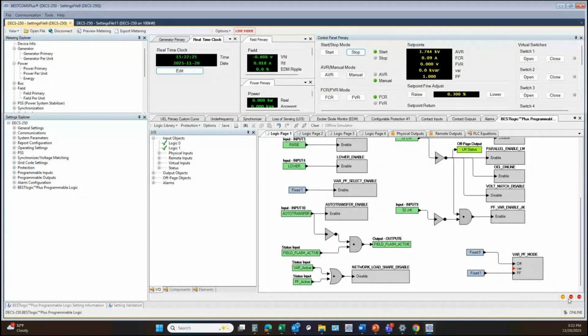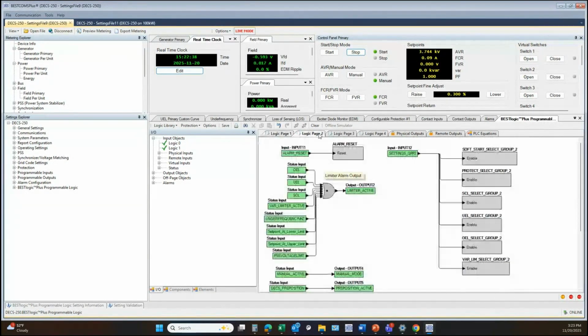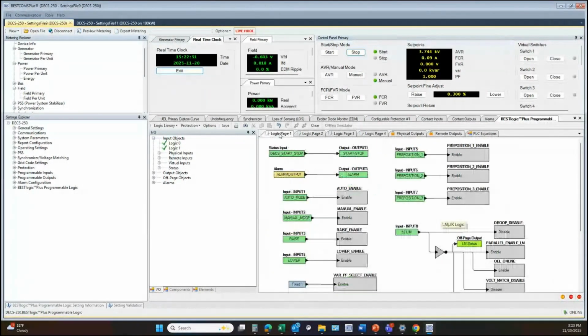Then I see that my logic is broken. This logic diagram status is red, the logic layer status is red, letting me know there's something severely wrong with my logic, and the unit won't be able to accept it this way. If I go to a different page, I can see the 3rd indicator is now green. That lets me know that the logic on this particular logic page is okay. But once I go back to that page that has the problem, then I see that that last indicator is also red again.